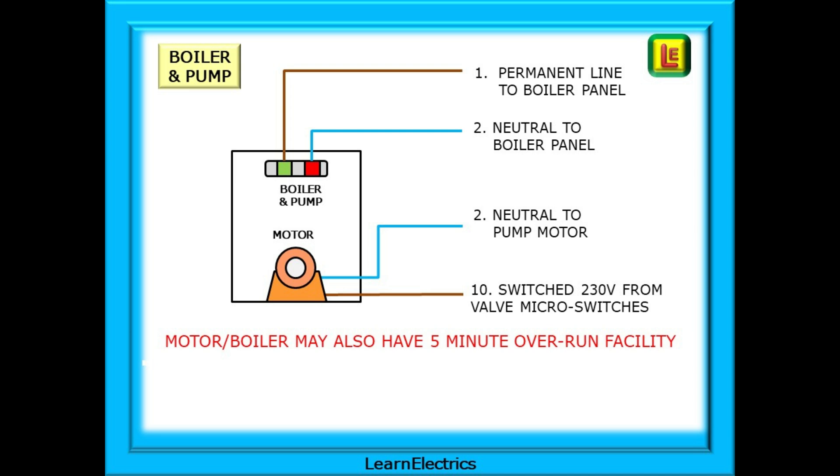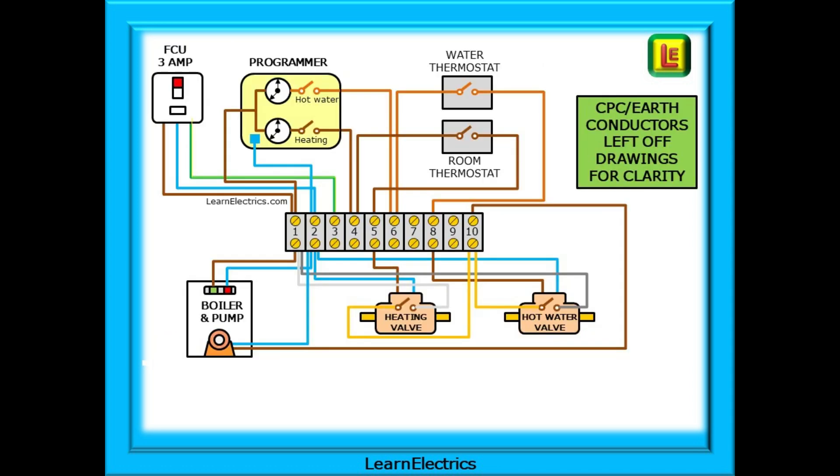It works in a similar way to the overrun for a bathroom extractor. And that is S-Plan. Hopefully you can now look at this wiring diagram and pick out the various components and the associated wiring for each of them. It is just a sequence of switches. One sequence for the hot water and another sequence for the room heating. Each has a programmer switch, a thermostat switch and a valve switch and unless all three switches are closed at the same time nothing will happen.